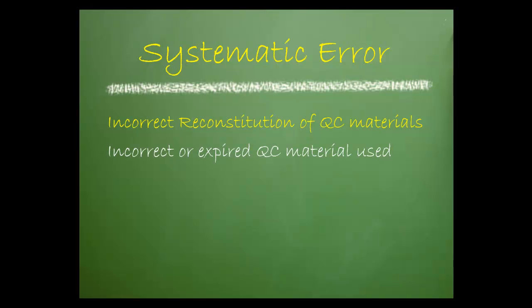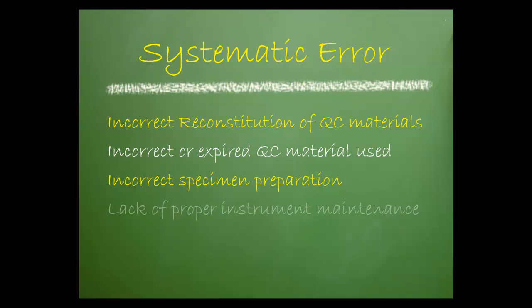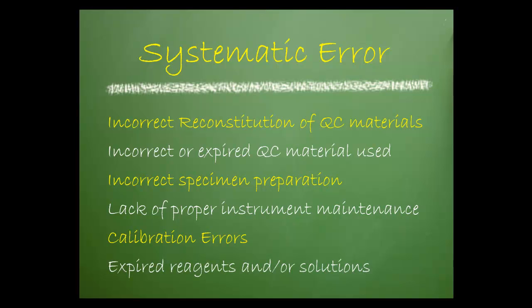Before we get into systematic allowable error, we need to understand systematic error. Systematic error in the laboratory setting is used to describe errors caused from instrument malfunction, tech error, and analytical factors. Examples include incorrect reconstitution of QC materials, incorrect or expired QC material, incorrect specimen preparation, lack of proper instrument maintenance, calibration errors, or expired reagents and/or solutions.